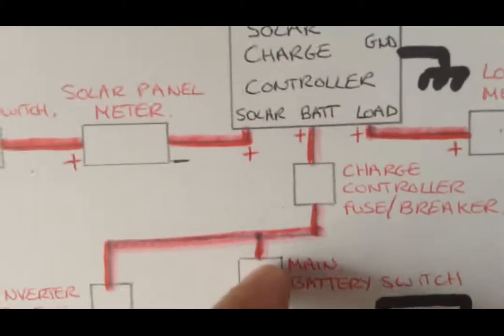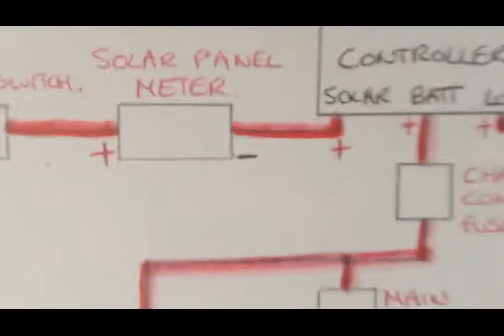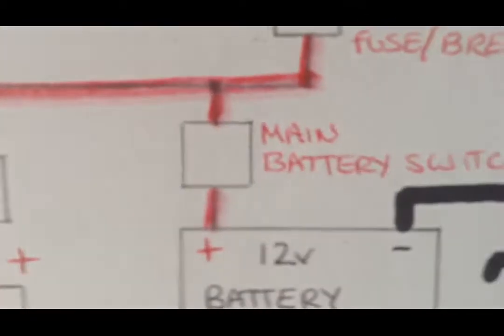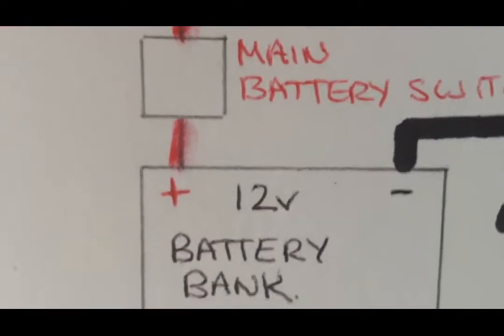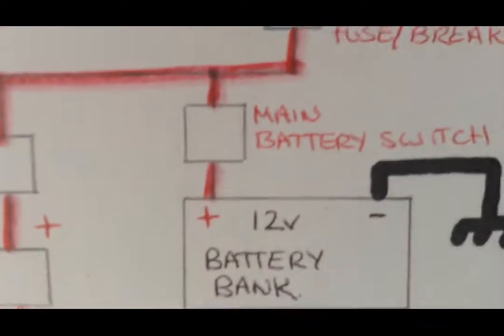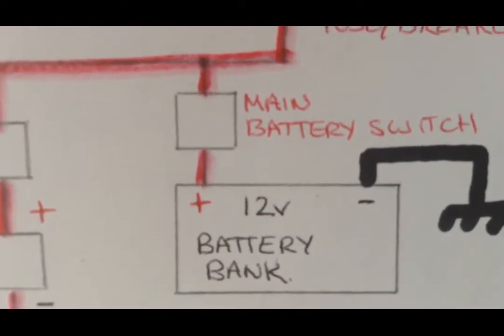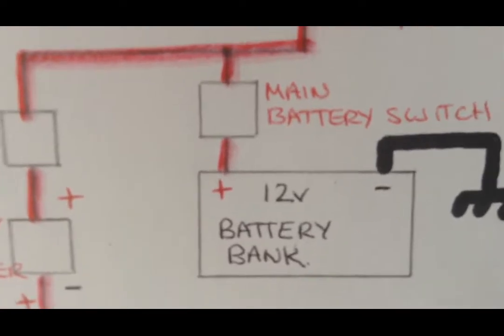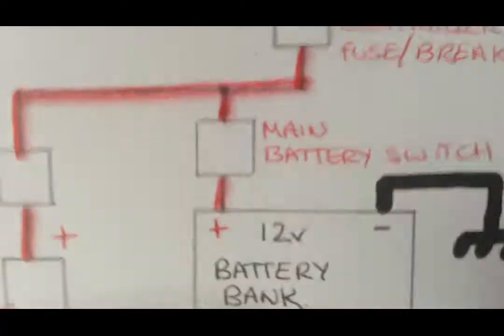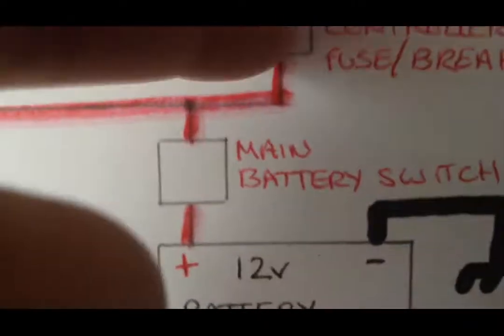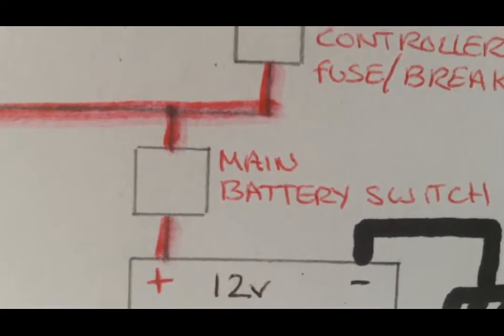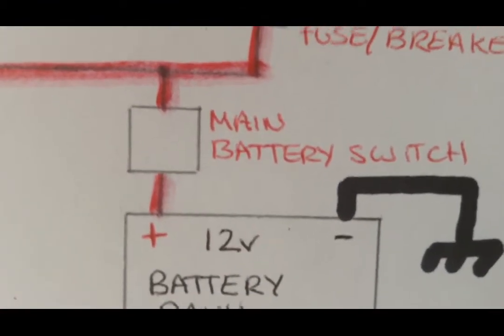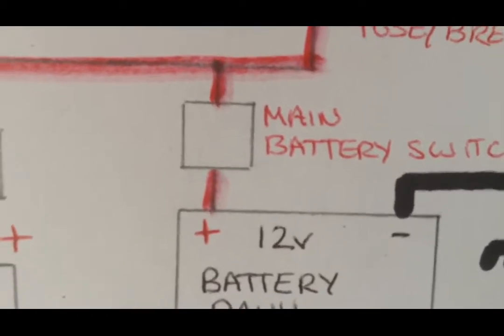So from the fuse or the breaker we go to a switch, the main switch. The main switch should be wired as close as possible to the battery or battery bank. I write battery bank here. You may have 1 battery, 2, 3, however many batteries you've got. This is the battery bank. The main switch and the fuse or breaker need to be as physically close as possible to the battery bank. So that's just a safety thing.